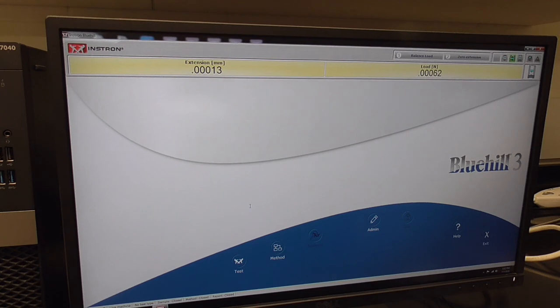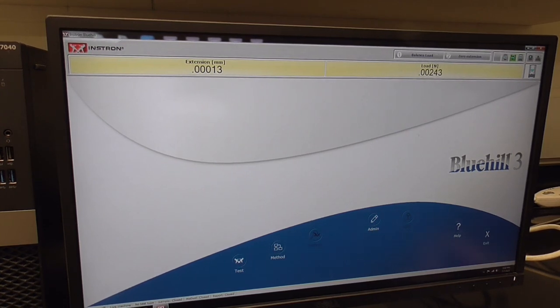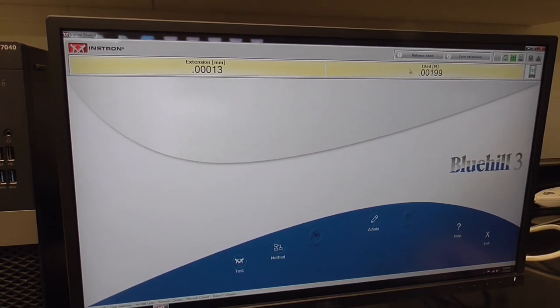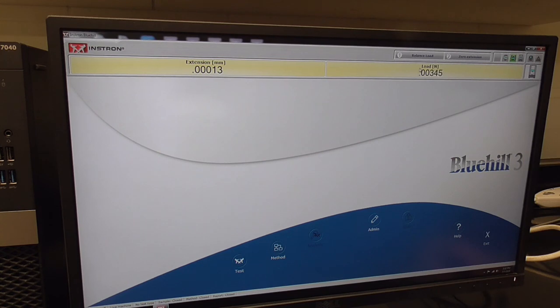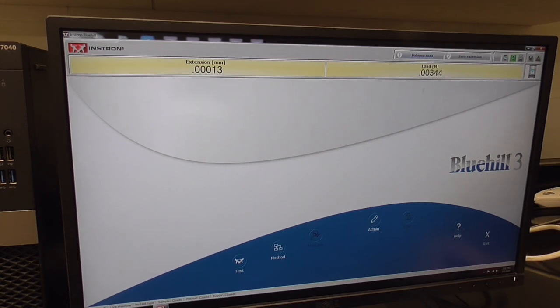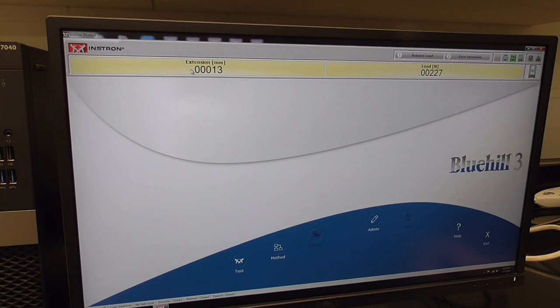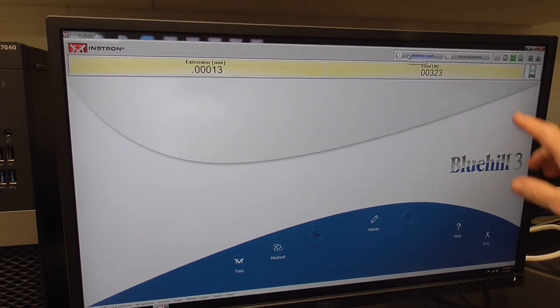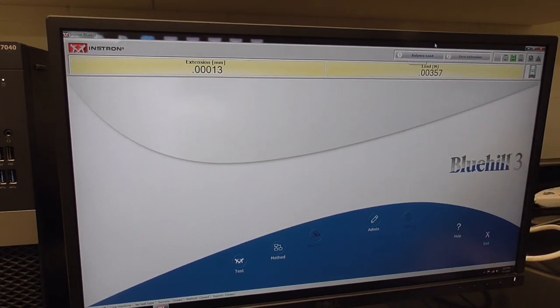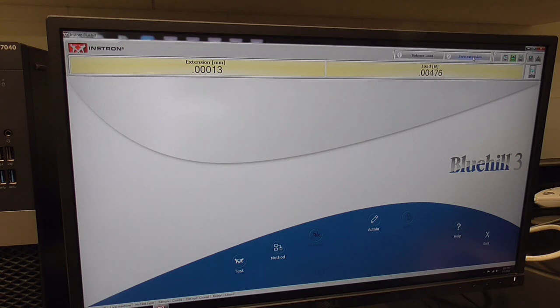Once you have the load cell calibrated, the load should read zero. If it doesn't, you can balance the load. You only need to calibrate the load cell once at the beginning of the day. Then if you need the load at zero, you just hit balance load and it'll go to zero. After we put the dog bone in, we may need to zero the extension, and that's done here on the upper toolbar: zero extension.